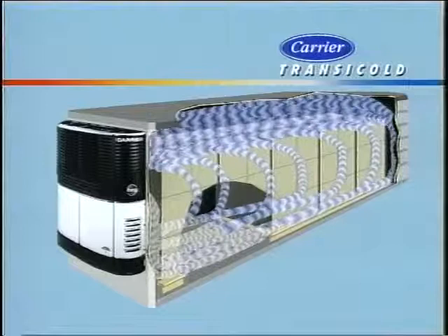Now check to see which mode the unit is operating in. Our unit is in continuous run from last trip. In this mode, the unit will run continuously and cycle between high speed and low speed and between heat and cool to hold box temperature at set point. Continuous run is generally used when hauling sensitive products such as produce. Continuous run operation provides continuous airflow inside the trailer and very close temperature control of the product.